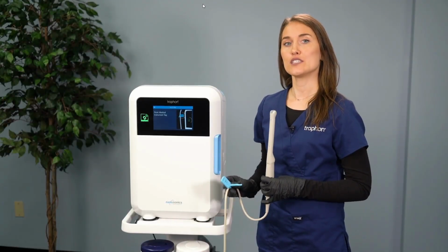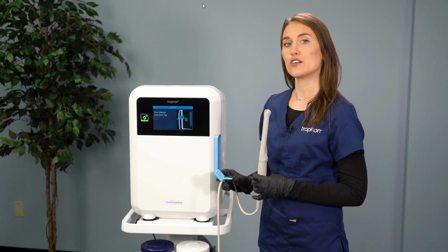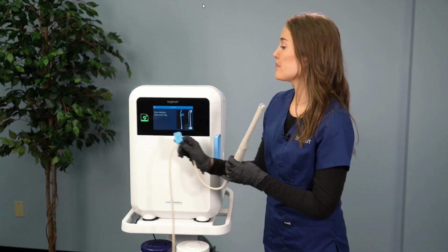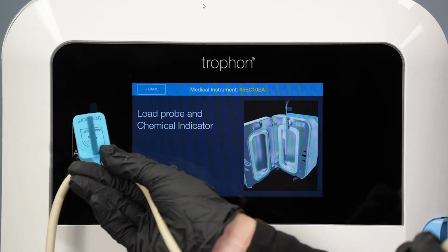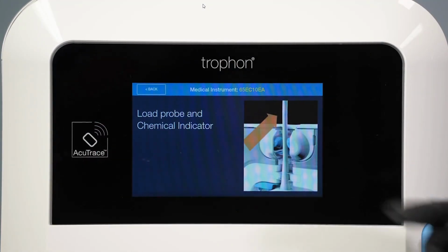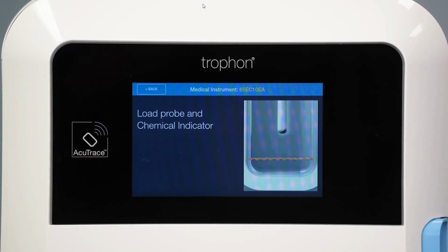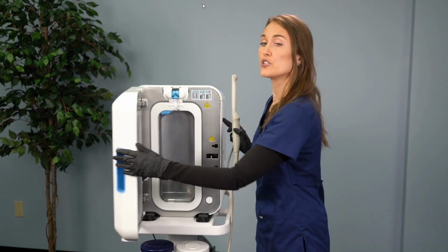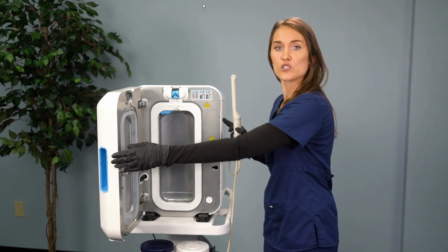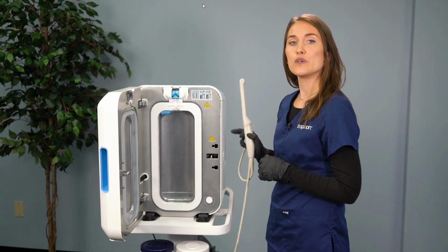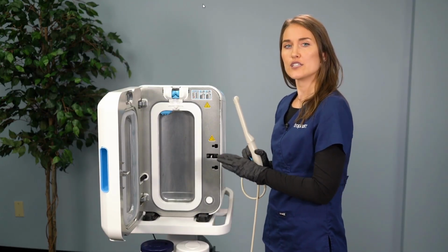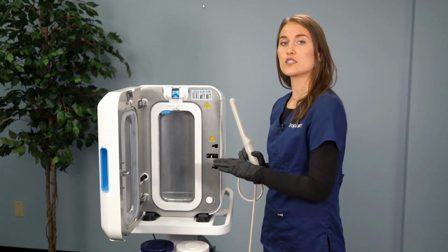First, scan the medical instrument tag into the AcuTrace RFID reader until you hear a beep. You'll then be instructed to load probe and chemical indicator, so you can go ahead and open your door. Once the door is open and you begin loading the probe into the chamber, use caution as the chamber may be hot or warm to the touch.